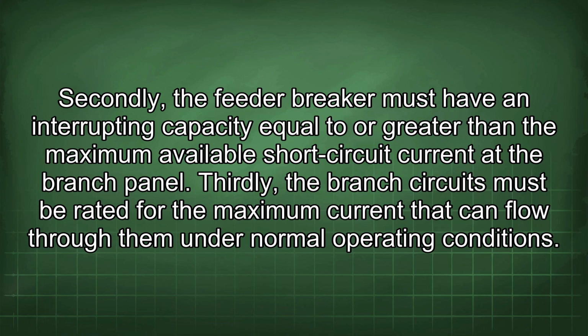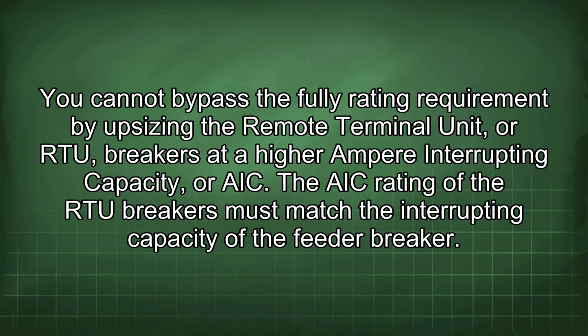Thirdly, the branch circuits must be rated for the maximum current that can flow through them under normal operating conditions. You cannot bypass the fully rating requirement by upsizing the remote terminal unit, or RTU, breakers at a higher ampere interrupting capacity, or AIC. The AIC rating of the RTU breakers must match the interrupting capacity of the feeder breaker.